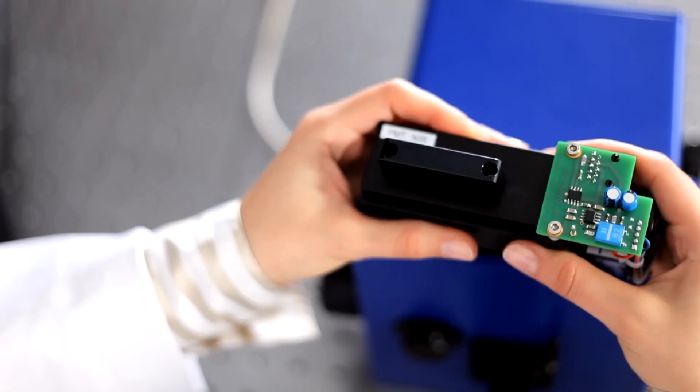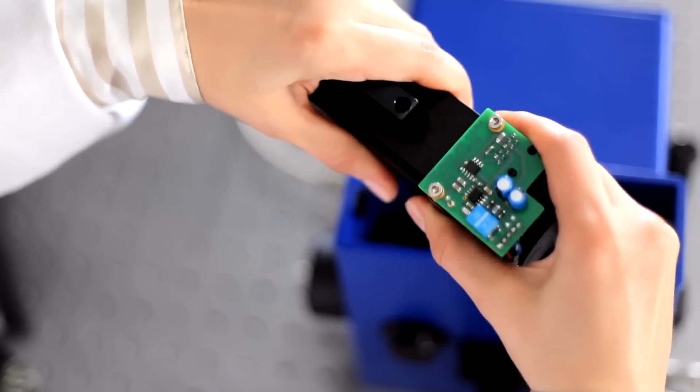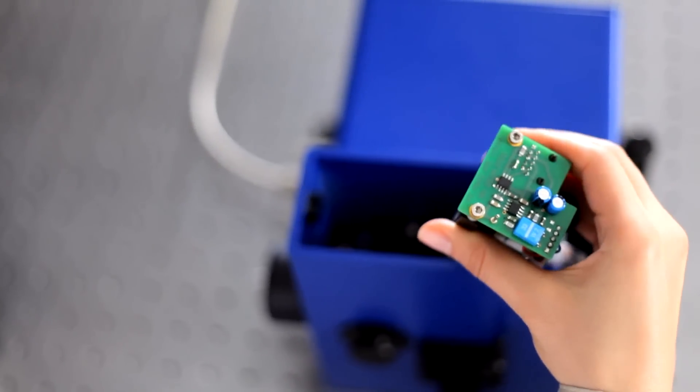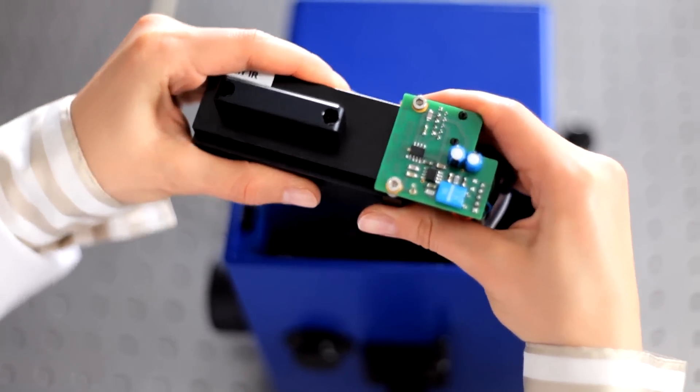To move the photomultiplier tube to a new detector unit, simply unplug the tube, like this. Then line up the pins with the unit you want to install, and snap them together.